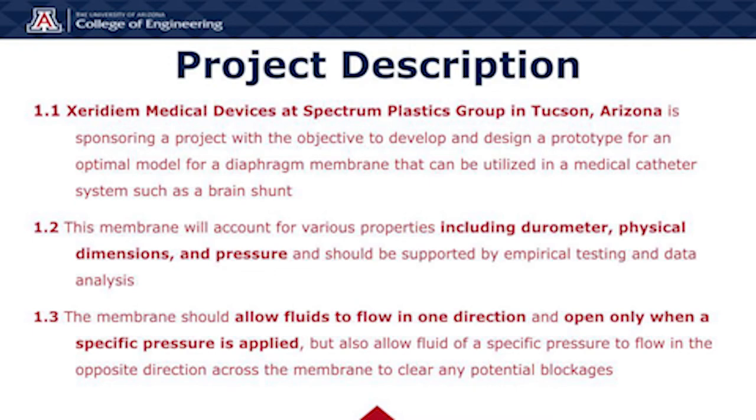Moving into the project description. Xeridiem Medical Devices at Spectrum Plastics Group in Tucson, Arizona is sponsoring a project with the objective to develop and design a prototype for an optimal model for a diaphragm membrane that can be utilized in a medical catheter system such as a brain shunt. This membrane will account for various properties including durometer, physical dimensions, and pressure, and should be supported by empirical testing and data analysis. The membrane should allow fluids to flow in one direction and open only when a specific pressure is applied, but also allow fluid of a specific pressure to flow in the opposite direction across the membrane so as to clear any potential blockages.